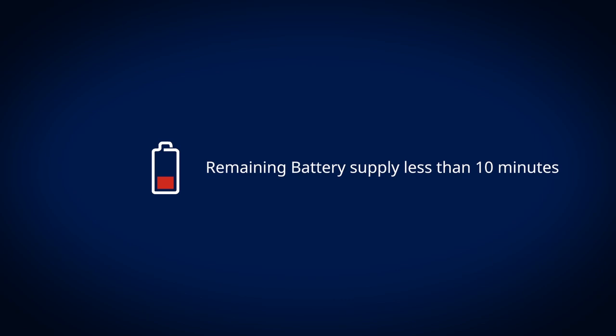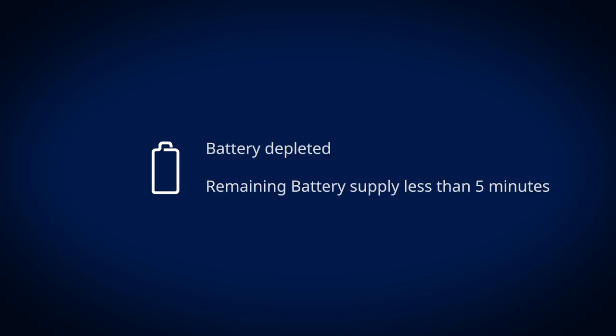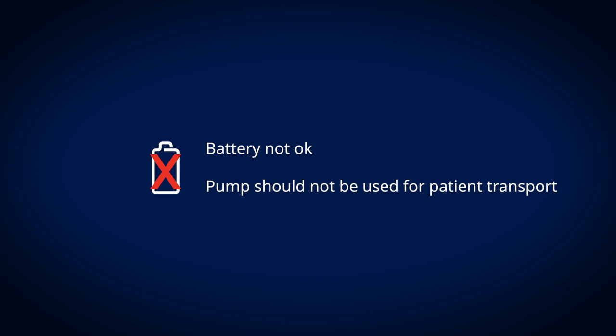If the battery icon is red, the status is okay, but the charge is estimated to be less than 10 minutes, and the battery less than 10 minutes alarm will occur. The black icon indicates the battery charge is depleted, the charge is estimated at less than 5 minutes, and the battery less than 5 minutes alarm will occur. If a battery icon with a red X is displayed, the battery is not okay. The pump should not be used for patient transport.